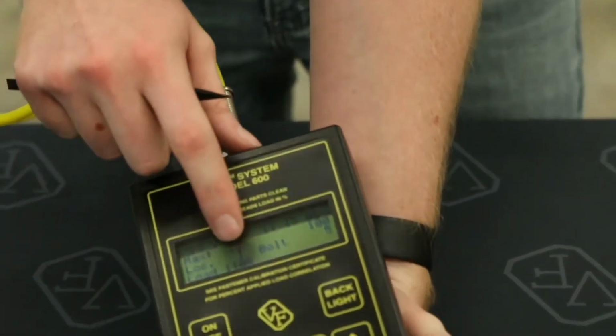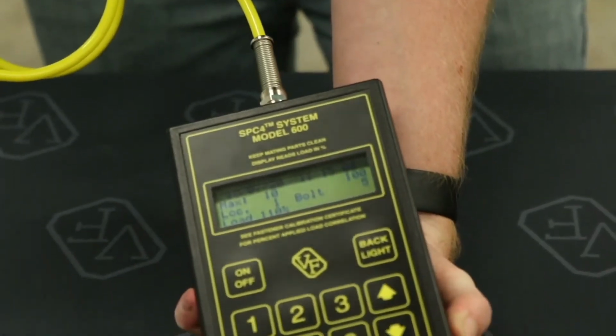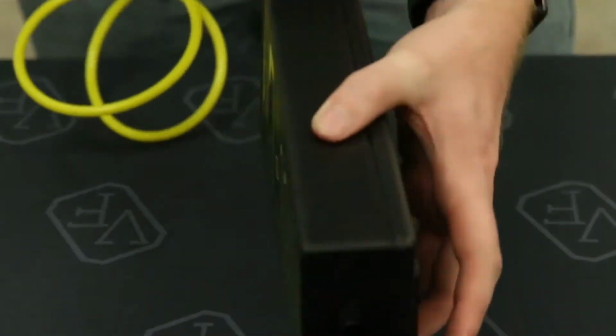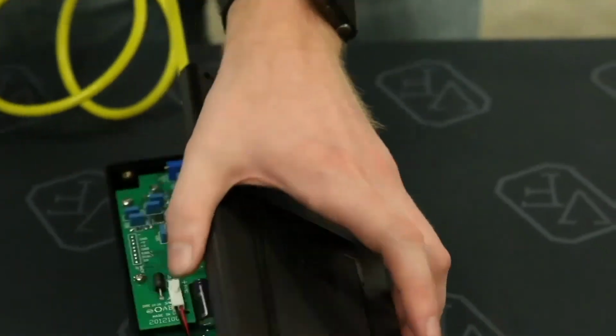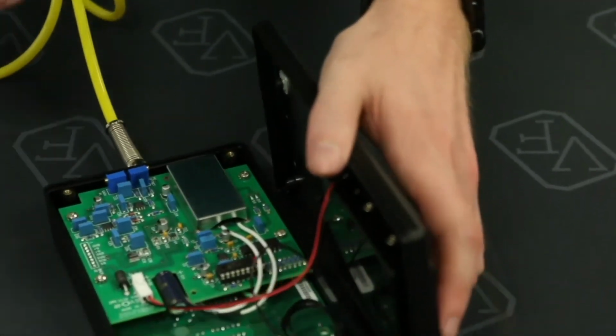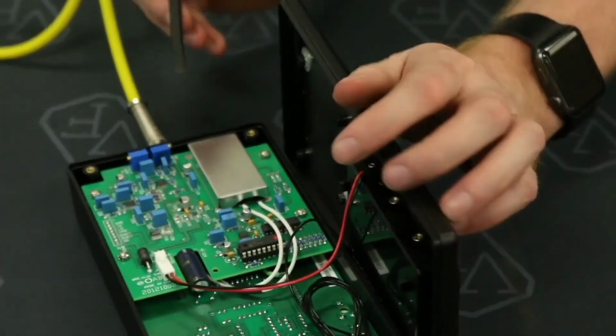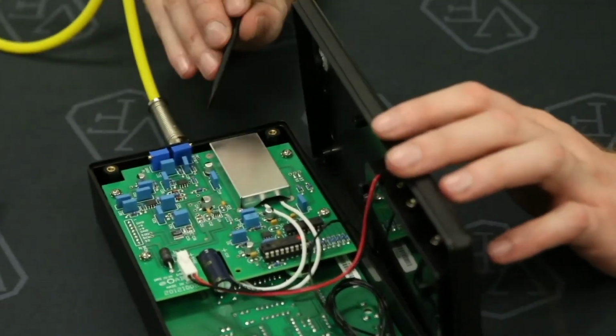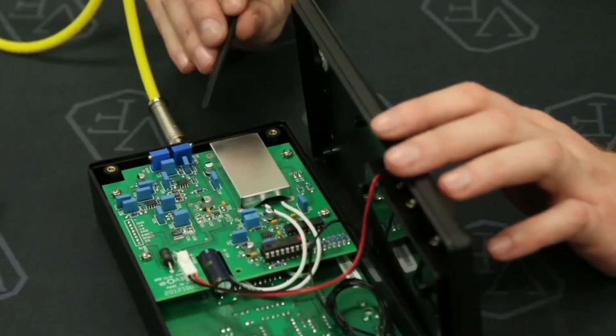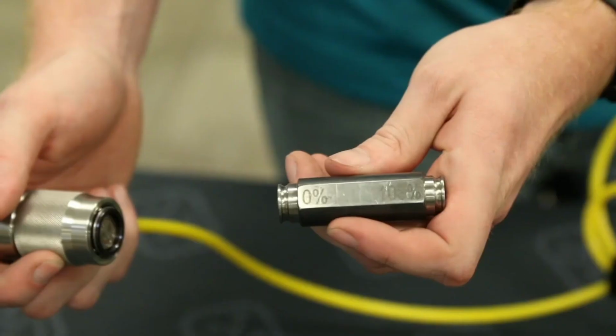If calibration is required, bring the 600A to a clean workbench. Remove the 4 enclosure screws found on the back of the unit. Carefully remove the rear of the enclosure and use caution not to inadvertently touch any internal components found inside the 600A. 2 blue potentiometers can be found inside the 600A.